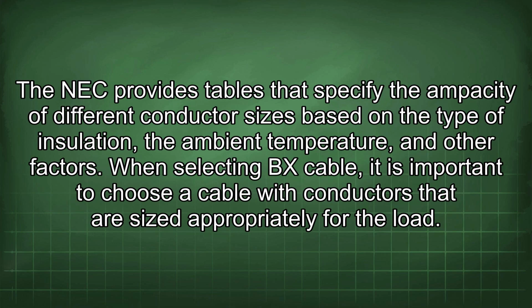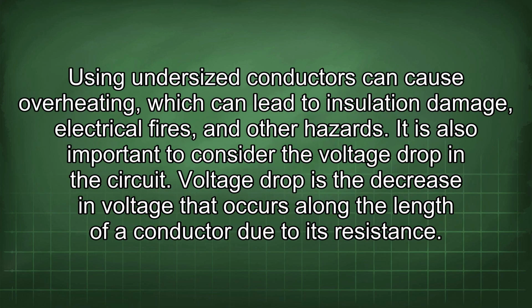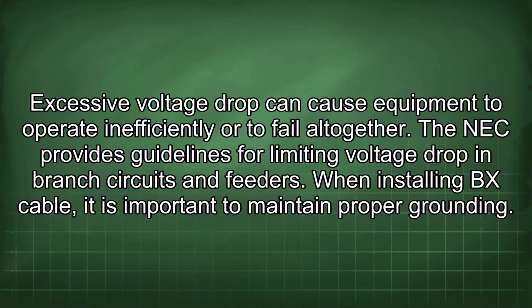The NEC provides tables that specify the ampacity of different conductor sizes based on the type of insulation, the ambient temperature, and other factors. When selecting BX cable, it is important to choose a cable with conductors that are sized appropriately for the load. Using undersized conductors can cause overheating, which can lead to insulation damage, electrical fires, and other hazards. It is also important to consider the voltage drop in the circuit. Voltage drop is the decrease in voltage that occurs along the length of a conductor due to its resistance. Excessive voltage drop can cause equipment to operate inefficiently or to fail altogether. The NEC provides guidelines for limiting voltage drop in branch circuits and feeders.